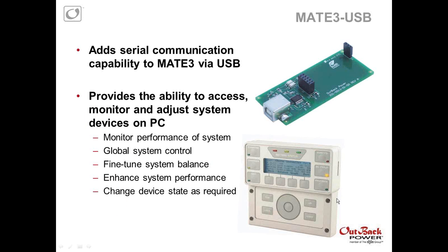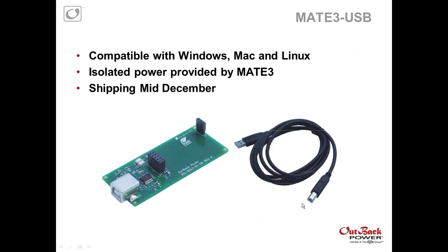The way that it is intended to be installed is you have a series of 4 screws here which would be undone, and it allows the back panel of the Mate 3 to come apart. Essentially it slides onto a set of prongs here and here on the actual control board of the Mate 3. And the USB Type B port now comes out through a bottom portion of the Mate. So your USB cord would plug in from the bottom.